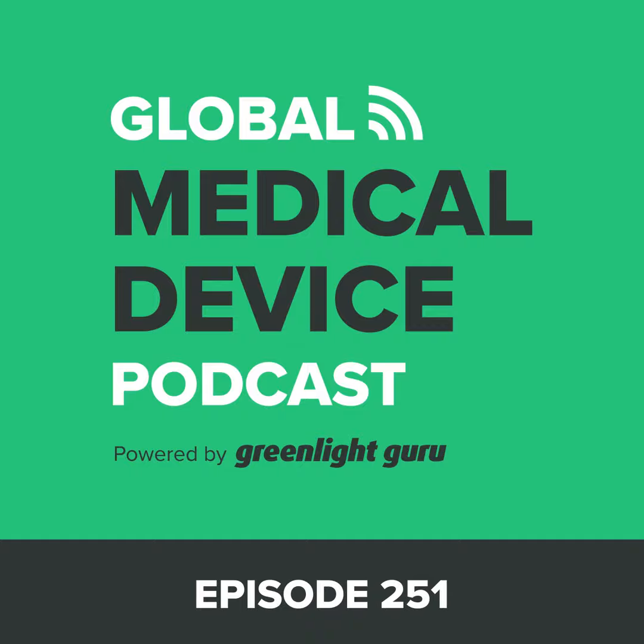So we talked about contract manufacturing in a previous episode as well. So the BOM, I mean, it seems obvious, I guess, but really nothing's obvious. Who owns the BOM in these different scenarios? That's a good question. The device manufacturer owns the BOM. You own the DMR. You're telling the contract manufacturer to build it for the DMR. Now, the contract manufacturer can give you lots and lots of help, but you're responsible for it.